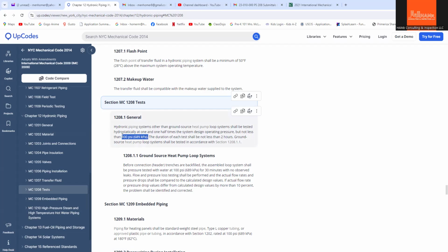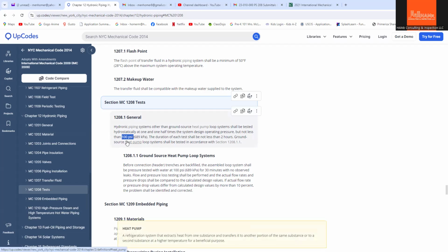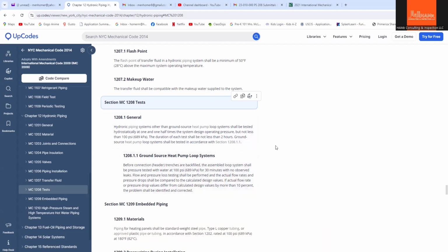If the new piping is connected to the existing system and you cannot test the whole system as new piping, it might create leaks elsewhere. Let's say you have a 10-story or 20-story building and you're only renovating one floor. If you test the whole piping, and you don't know how long this building has been existing, maybe 20 or 50 years, it might leak somewhere else, and you don't want that to happen. So in that case, you need to refer the matter to the building engineer, unless the contractor can isolate the new piping to be tested at 100 psi. So it's a case by case basis.